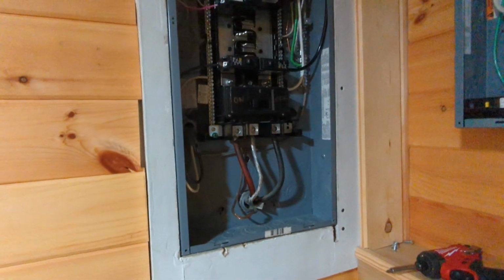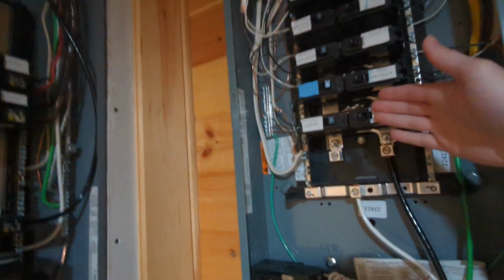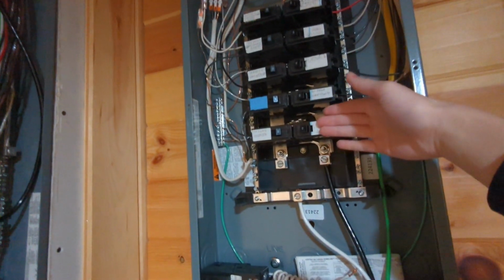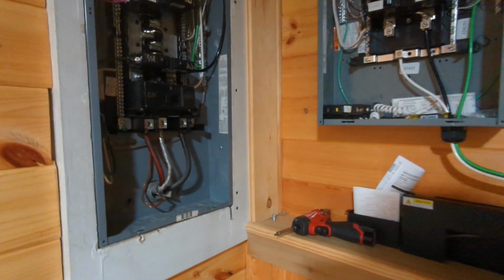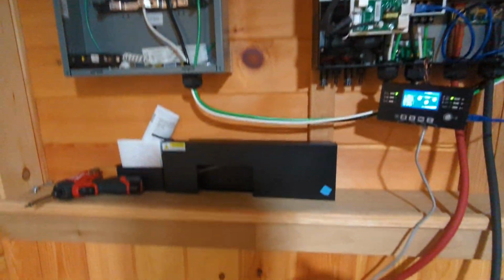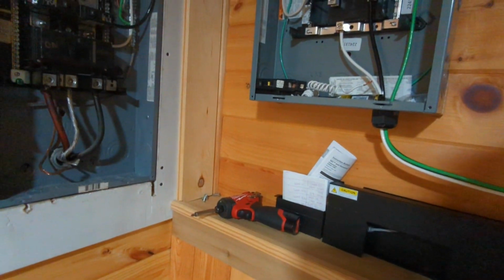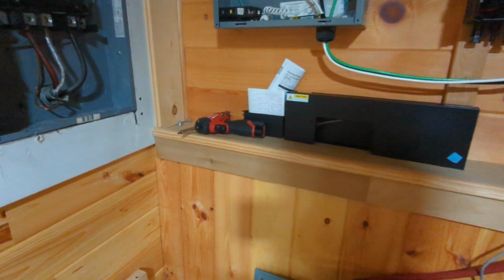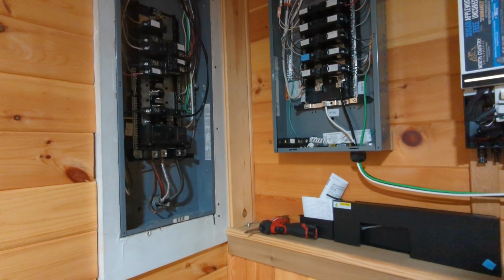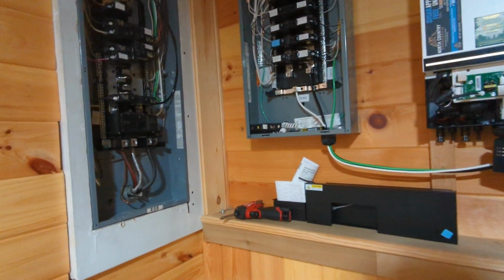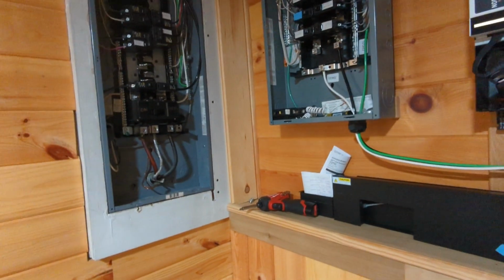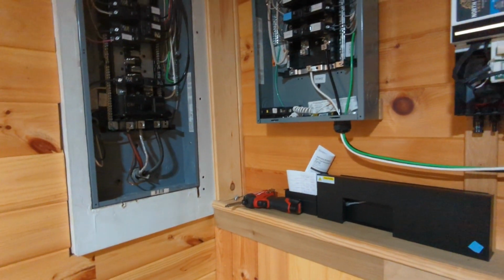And I could use the generator directly as an AC input for any active load that is on this panel right here. And then of course, if the battery was not at a full state of charge, the inverter would also use some of that wattage or some of that power from the generator and start charging the battery as well. I can set the charge rate in the inverter settings to 50 amps at the battery voltage, 2,500 watts of power going to the battery.